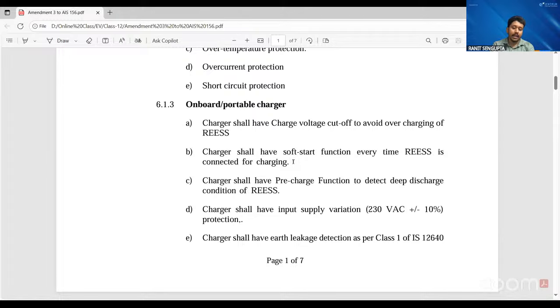The fifth point is that the charger shall have earth leakage detection. What is earth leakage detection? We give a line, a neutral, and an earthing point. In the whole charging industry, for a portable charger, there is a connector type arrangement with cables having earth leakage detection and protection systems, meaning an on-off switch. Suppose leakage current is flowing from line to earth, or neutral to earth. If it detects any kind of leakage current, it will switch off the charging from the input side itself, not the output side. Before we push power to the input for AC to DC rectification, we use this type of earth leakage detection circuit.